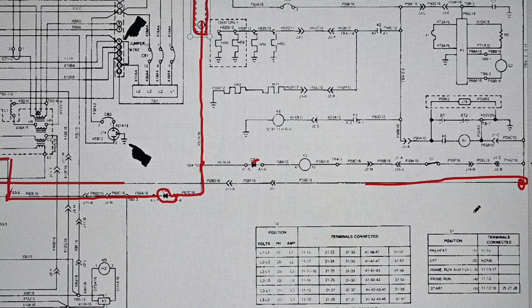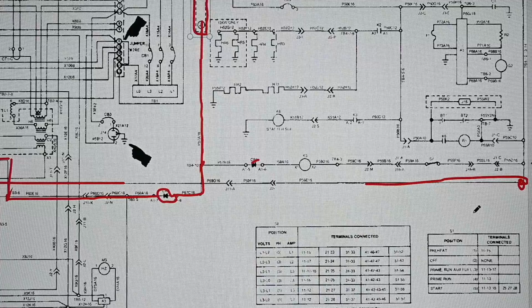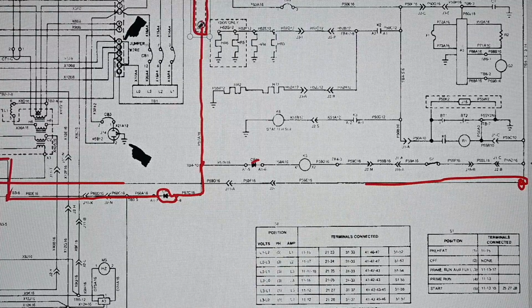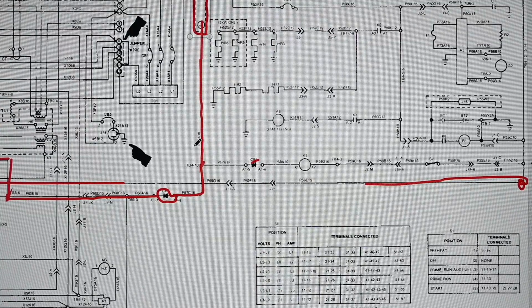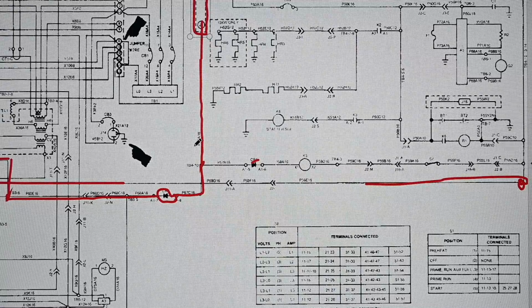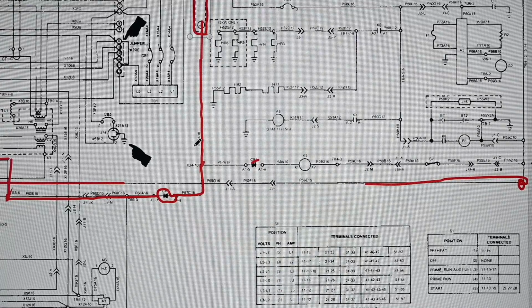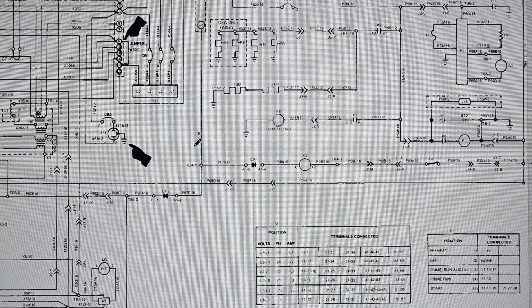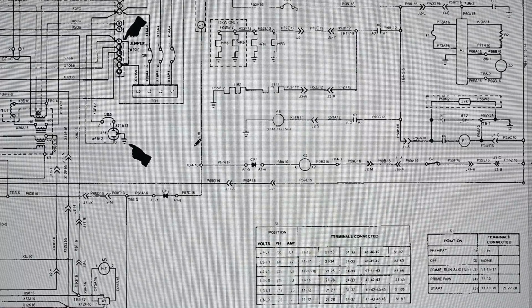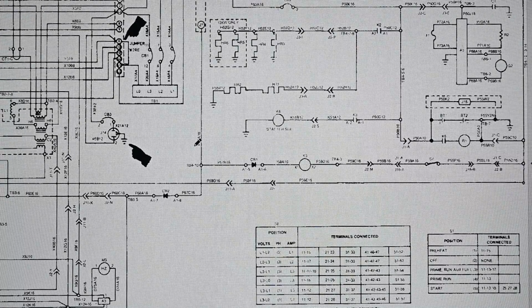That completes the circuit, and as long as voltage is being applied off of this start switch, you'll have voltage applied over to the field, and it's flashing the generator, helping it build up that initial voltage. So now let's look at how the voltage regulator actually begins to take over and control the voltage.